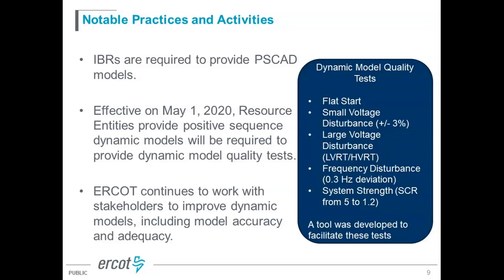When a dynamic model is provided to ERCOT and the transmission company in the ERCOT region, the associated model quality test needs to be provided as well. The model quality test will include a flat start and a small voltage disturbance, for example plus or minus 3% voltage deviation. Also, a large voltage disturbance to demonstrate their capability from LVRT to HVRT, and the associated frequency disturbance response of the dynamic model. As an example, we apply a 0.3 Hertz deviation to see whether the model responds properly to the frequency deviation.